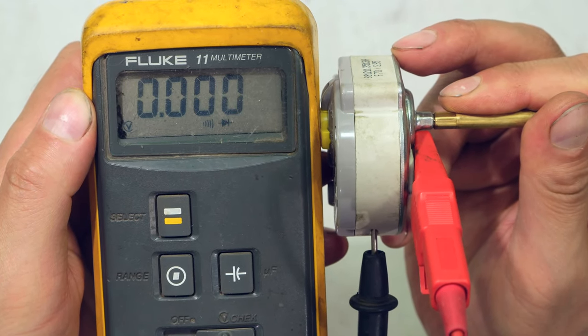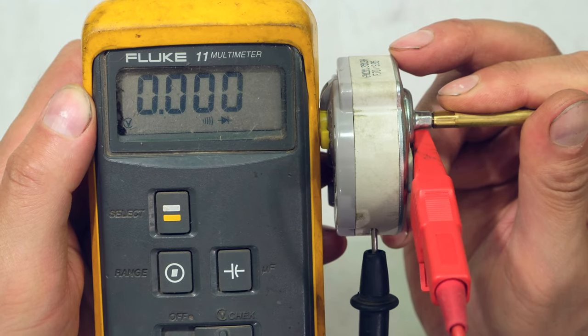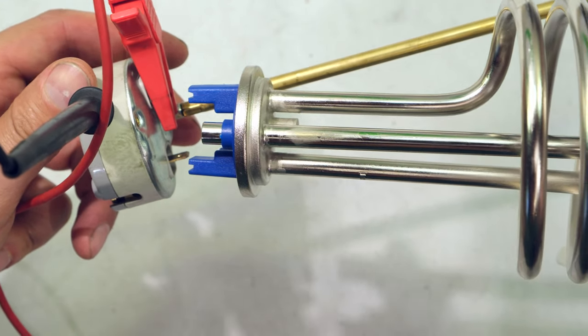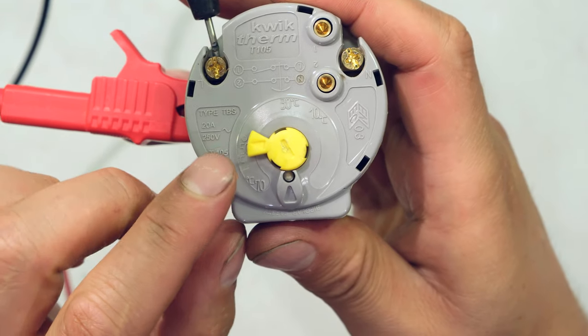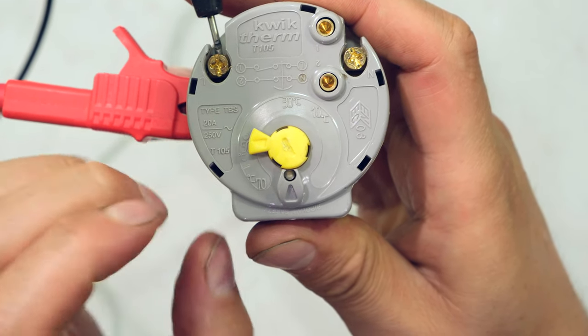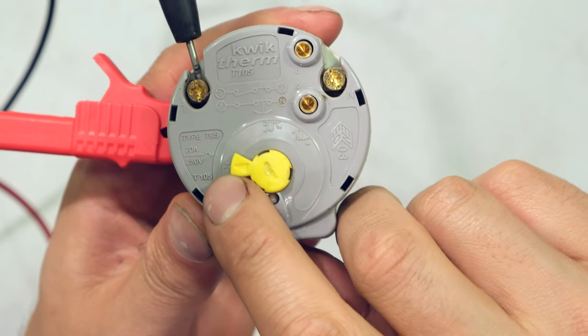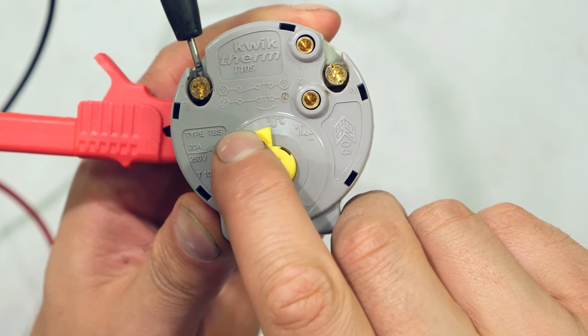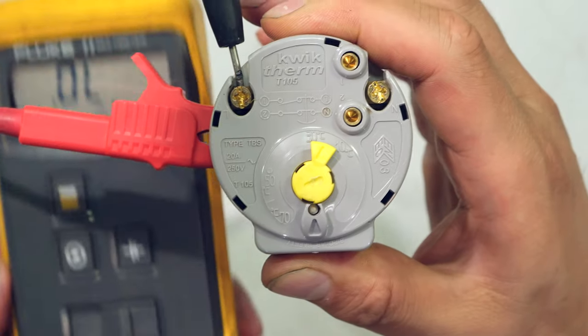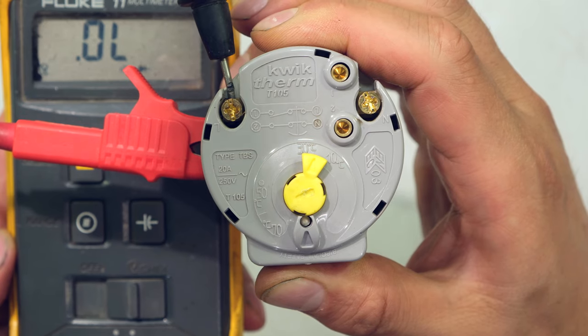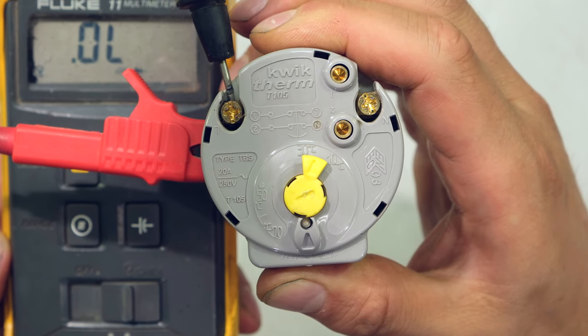That would mean that current would be flowing through this element. The reason why is because it's set to 50 degrees and the room temperature here is only about 22 degrees. If I reduce this below about 20 degrees, my meter stops making that noise and it's telling me it's an open circuit. An open circuit is now telling me that the thermostat is not going to allow current to flow.